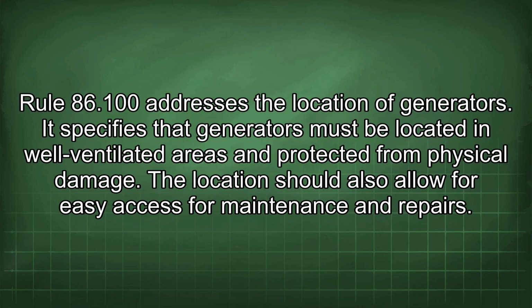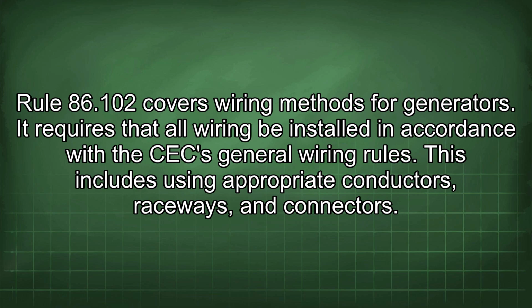Rule 86.100 addresses the location of generators. It specifies that generators must be located in well-ventilated areas and protected from physical damage. The location should also allow for easy access for maintenance and repairs. Rule 86.102 covers wiring methods for generators. It requires that all wiring be installed in accordance with the CEC's general wiring rules. This includes using appropriate conductors, raceways, and connectors.